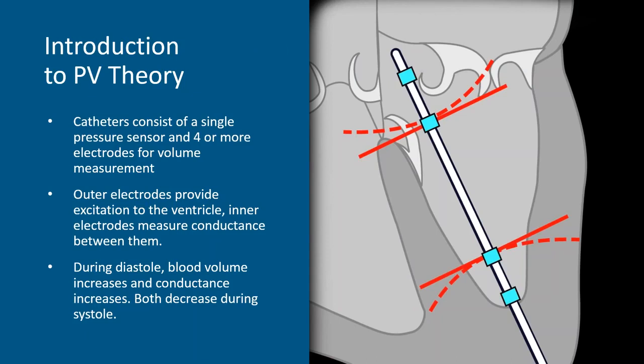As previously mentioned, the conductance catheter has really emerged as the sole method to provide instantaneous pressure volume data. It essentially consists of 4 or more electrodes that you can see there in the blue color. The outer electrodes inject a current into the left ventricle, and the inner pair of electrodes are used to measure the conductance, or the voltage drop across those 2 electrodes.